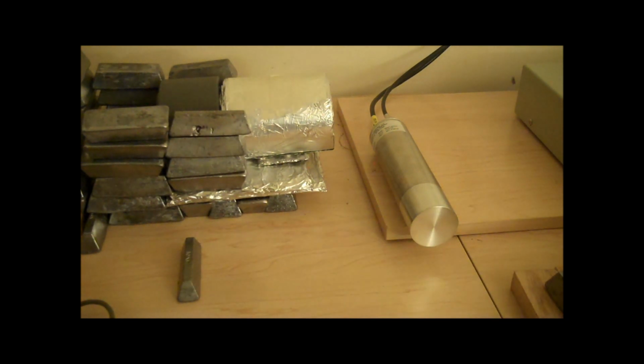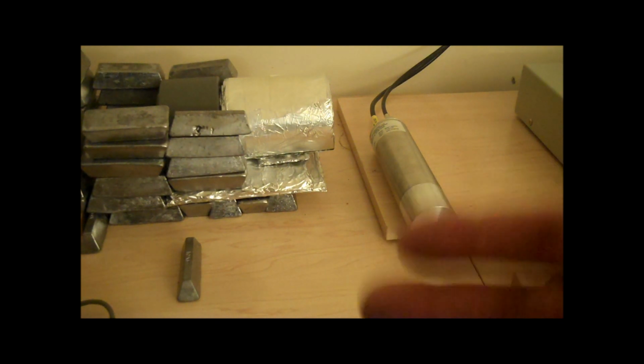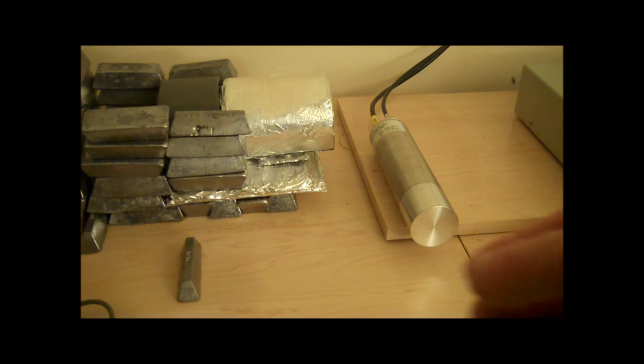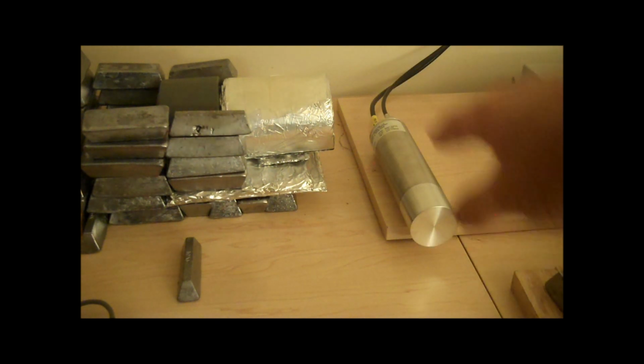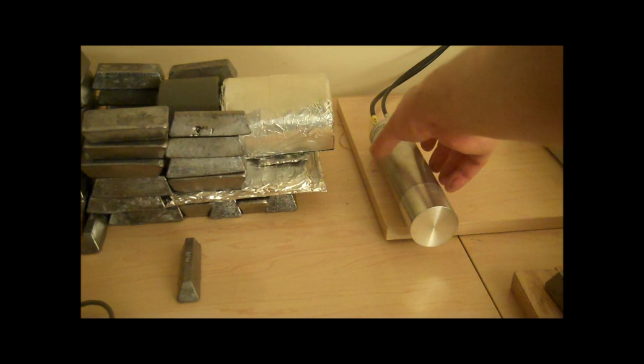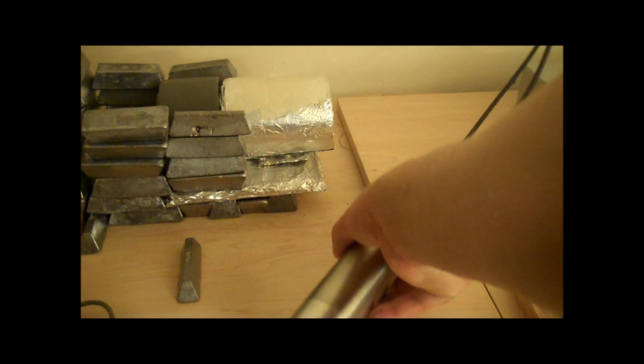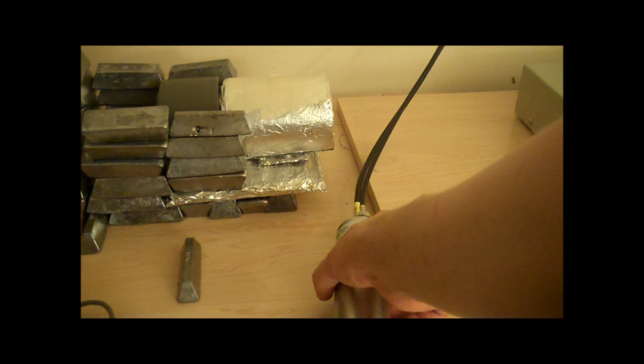If you're wondering, the reason that there's lead all over the place surrounding the detector, or when it's inserted, is because all background radiation must be blocked to make sure that what this sees is as much of the sample as possible and as little of anything else as possible. Let me put this detector where we can look at it for a moment, and let me put the camera on it and explain how it works.